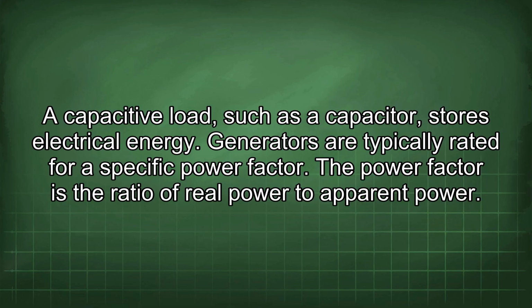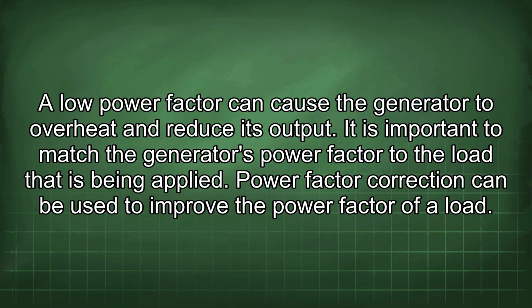Generators are typically rated for a specific power factor. The power factor is the ratio of real power to apparent power. A low power factor can cause the generator to overheat and reduce its output. It is important to match the generator's power factor to the load that is being applied.